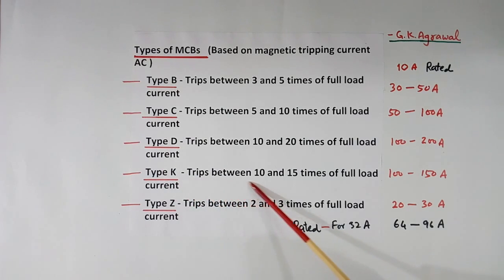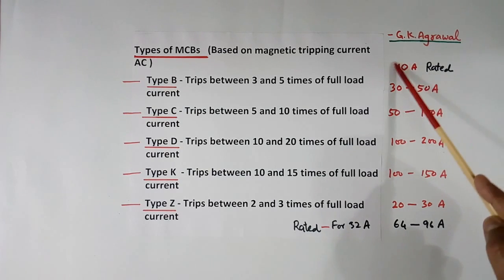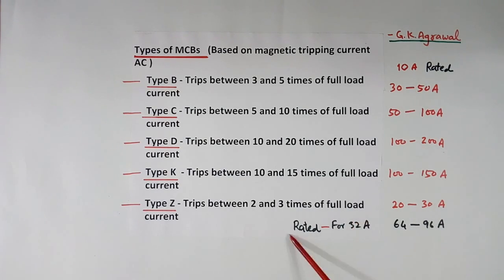Type K trips between 10 and 15 times. 10 times means 100 of this, 15 times means 150 A of this. So 100 to 150 A. Similarly type Z will trip between 2 and 3 times. 2 times of this means 20 A, 3 times means 30 A. So type Z will trip in the 20 to 30 A range, provided rating is 10 A. For 32 A rated current, 2 times will be 64 A and 3 times will be 96 A. So type Z, 32 A MCB will trip in range of 64 to 96 A. That is what I just showed.